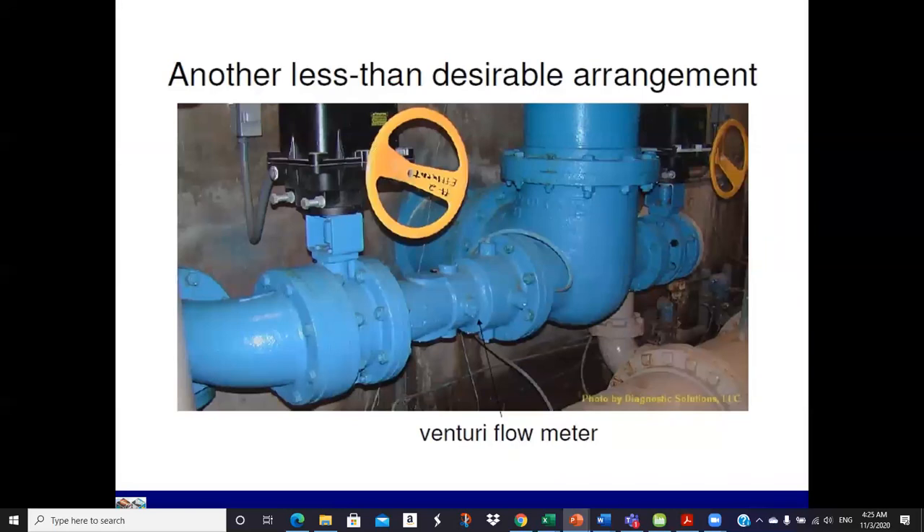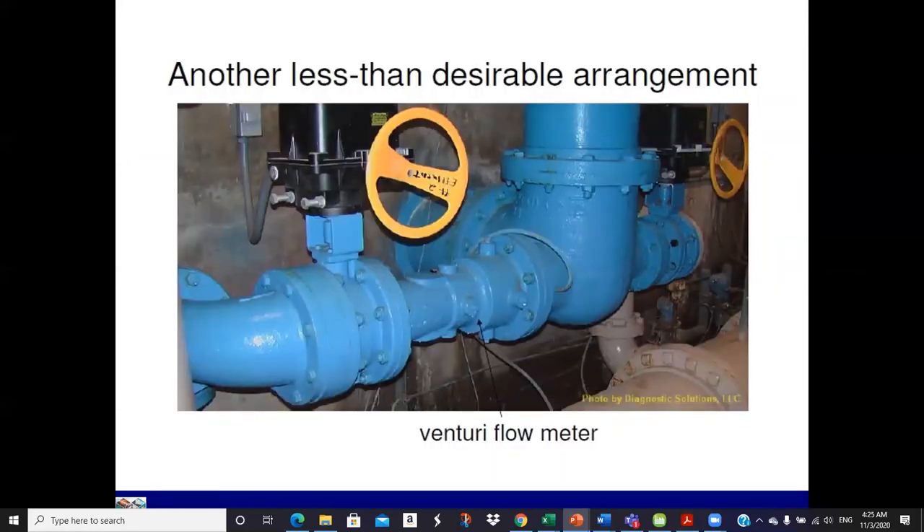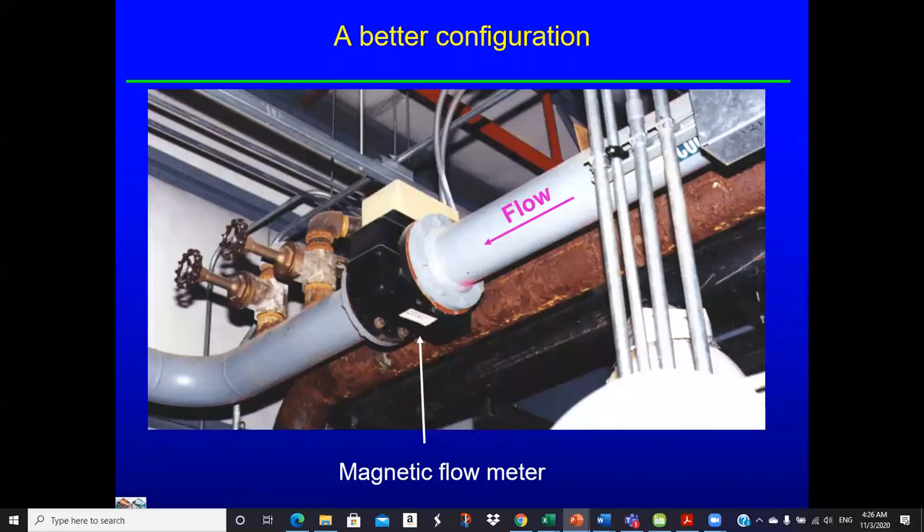Here's another example — a venturi flow meter. Again, you've got turbulence all over the place in your velocity profile, and you can't expect accuracy from a meter like that. Here's a better configuration: we've got a long run before the meter and a pretty good run after the meter. The two valves on the downstream side are closed. That's helpful.